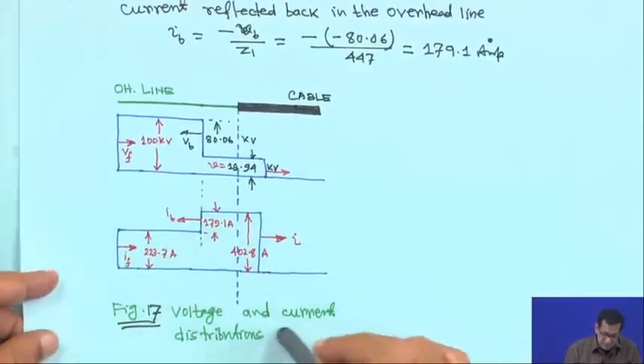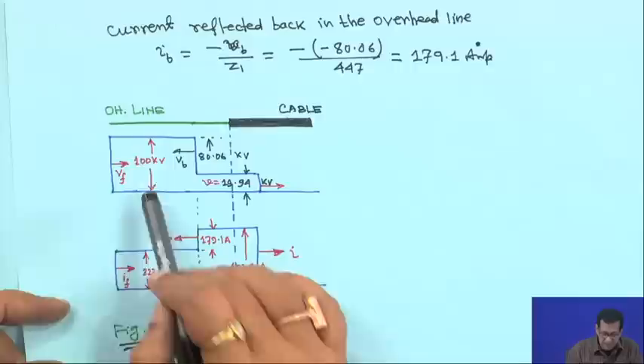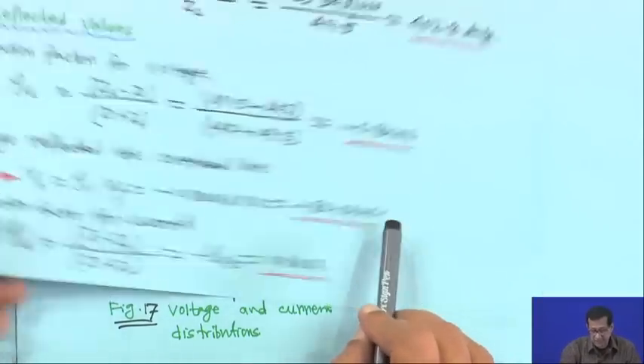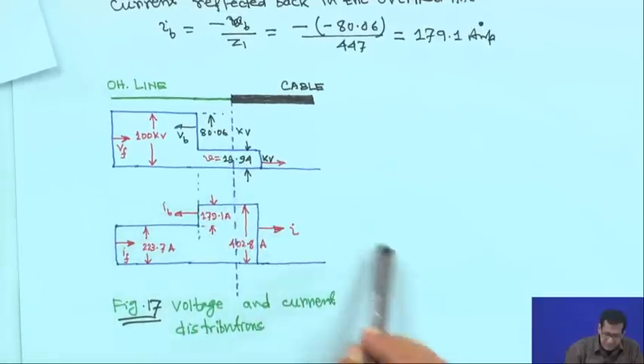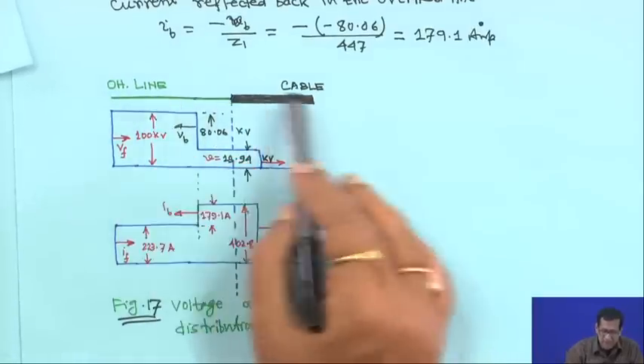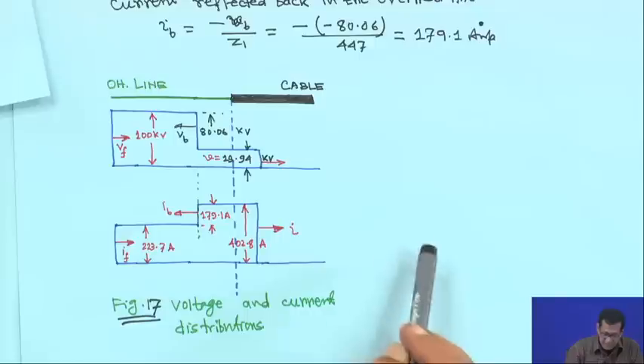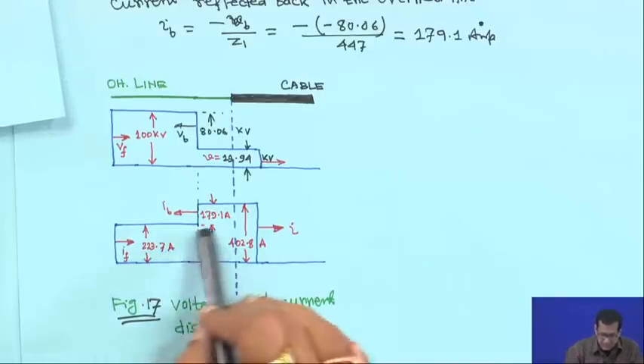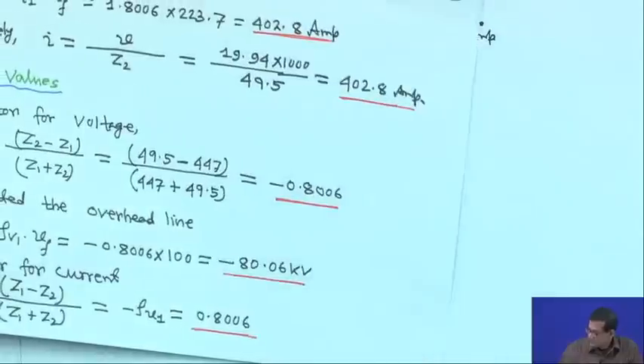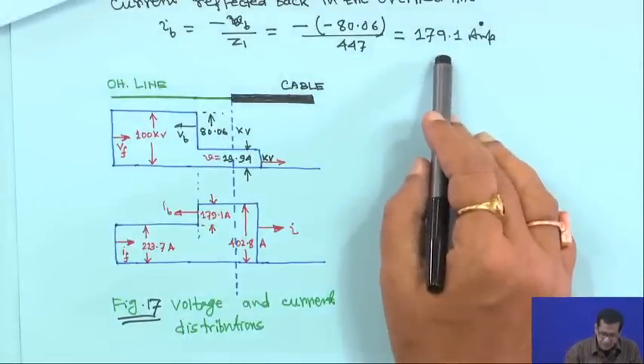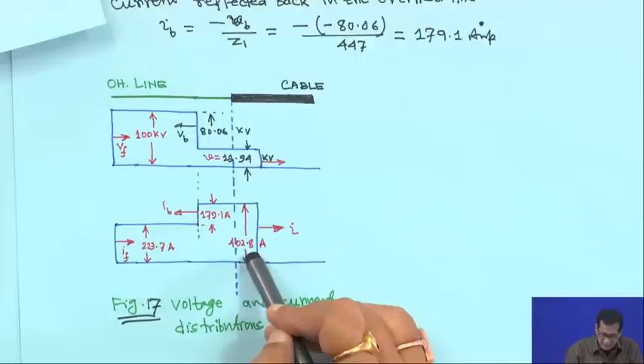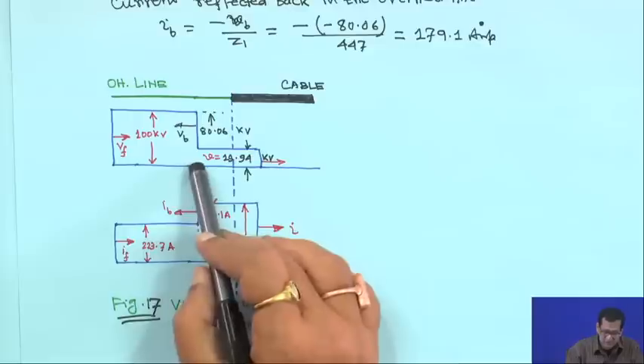The diagram shows voltage and current distribution. The initial travelling wave is 100 kV, but 80.06 kV reflects back as −80.06 kV. The resultant at the junction is 19.94 kV. For current, the incident is 223.7 amperes plus reflected 179.1 amperes, giving 402.8 amperes as the transmitted current wave.